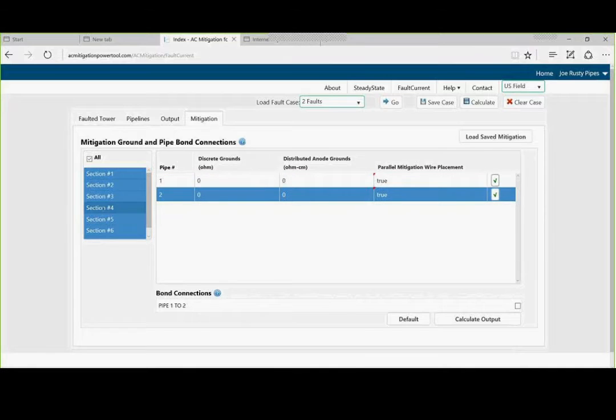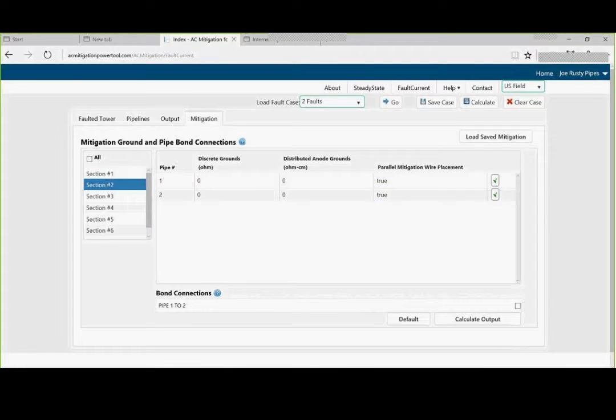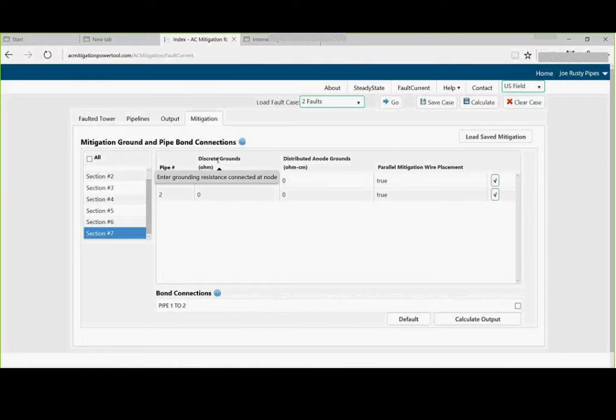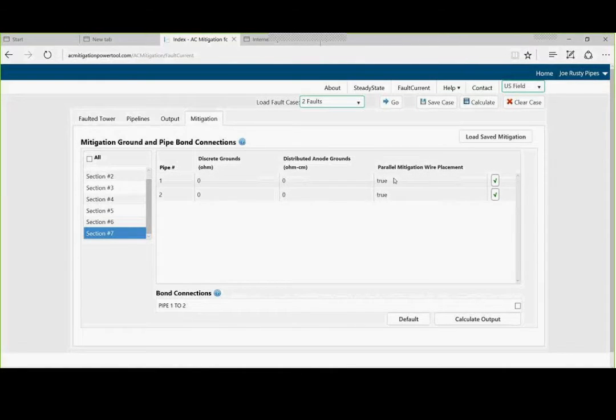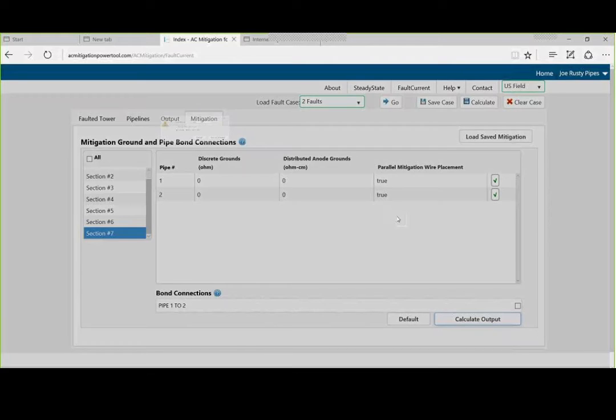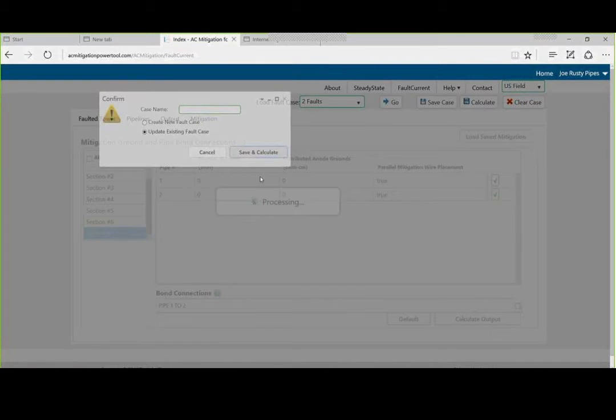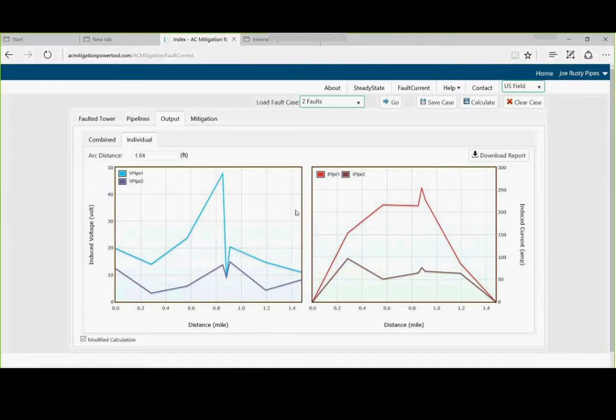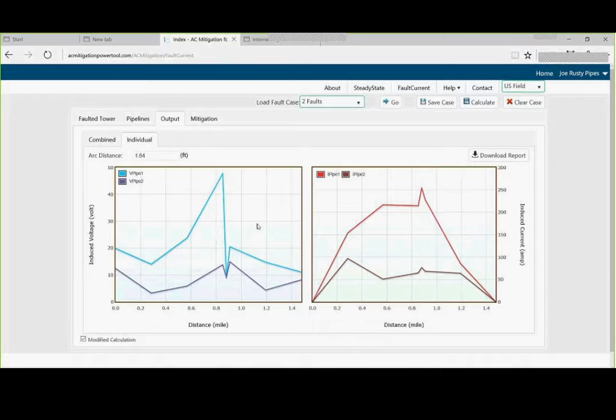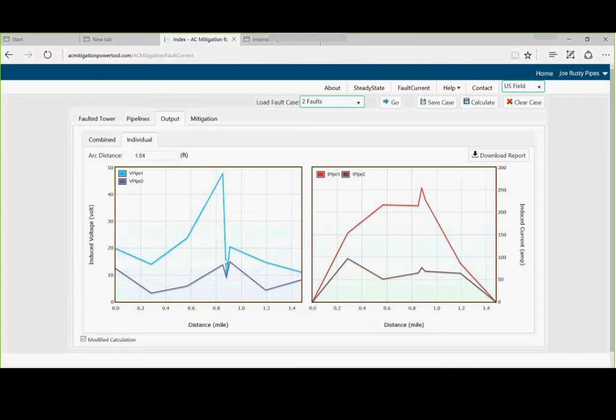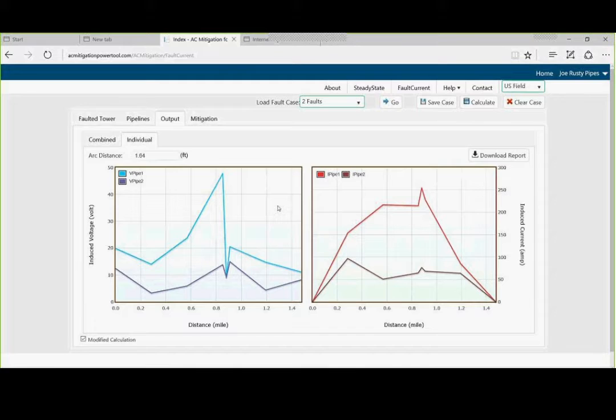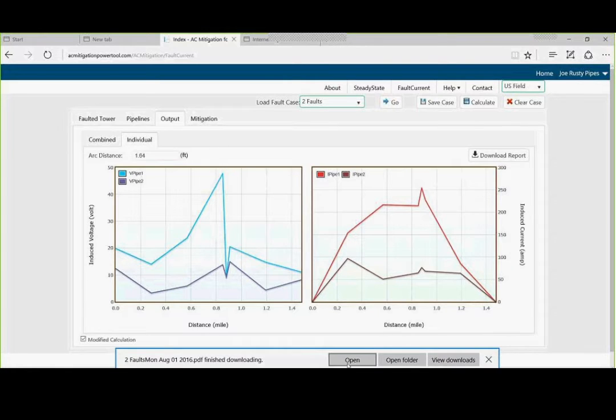Now we'll check it. We want to make sure that they're all checked. So we have a contiguous parallel mitigation wire on both lines. We can calculate the output. And you notice we brought the voltages down. So this will tell us that our only area of concern is at about almost 0.9 tenths of a mile. We have just completed the entire mitigation strategy. And of course you can save it.